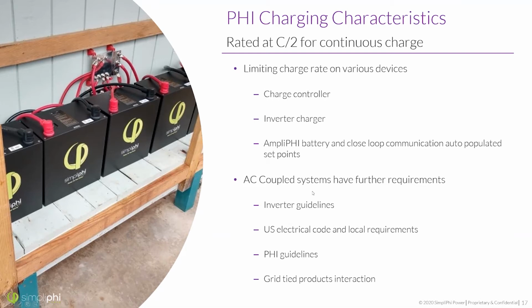So if you've got an existing grid tied array that you're adding a battery system to with AC coupling, you need to keep in mind that you can't just set the limit. You need to follow guidelines for sizing. I would just say there's inverter guidelines, there's code guidelines, and then there's our guidelines. Look in our manual if you're AC coupling.